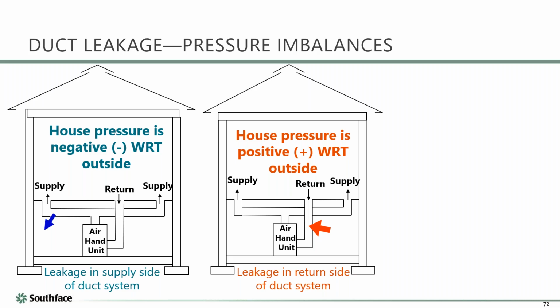I recommend you zero the gauge, baseline it, make it read 0, and go over to the air handler and turn the fan from auto to on. It'll make the blower turn on, and watch your pressure. If your house pressure goes negative, it means you have a lot of supply leaks. If your house pressure goes positive, it means you have a lot of return leaks.